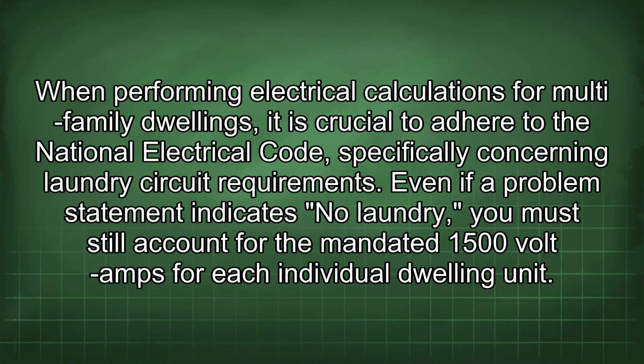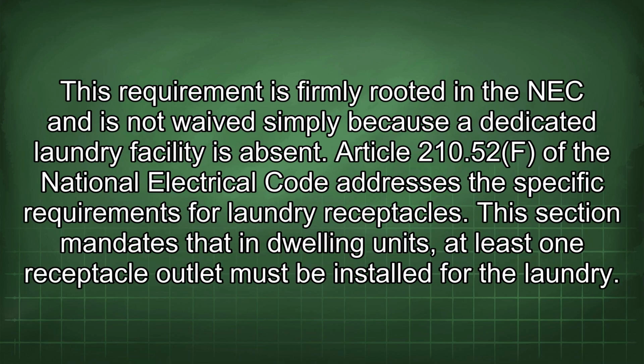When performing electrical calculations for multi-family dwellings, it is crucial to adhere to the National Electrical Code, specifically concerning laundry circuit requirements. Even if a problem statement indicates no laundry, you must still account for the mandated 1500 volt amps for each individual dwelling unit. This requirement is firmly rooted in the NEC and is not waived simply because a dedicated laundry facility is absent.